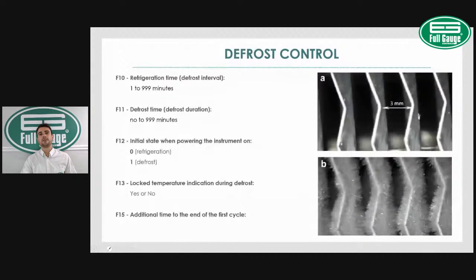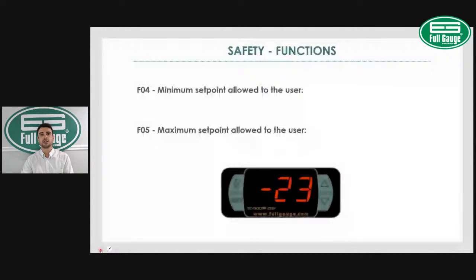Let us look at the safety functions. What are the safety functions loaded with the 512? You have a minimum and maximum set point threshold. The purpose of that is to prevent end users from changing the set point to a crazy condition. Let's put it this way. For example, I have my system working from 32 to 36.